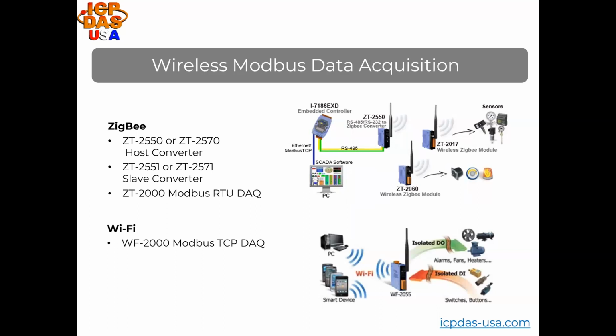Wireless Modbus data acquisition equipment helps with getting information where wiring is inconvenient. ZigBee is a self-organizing mesh network that supports different topologies, including star, cluster, and tree. ZigBee networks have one ZT2550 or ZT2570 host coordinator that coordinates the communication path in the network. Both our host coordinator converters have an RS-232, RS-485 port for serial communication. The ZT2570 has an Ethernet communication option.